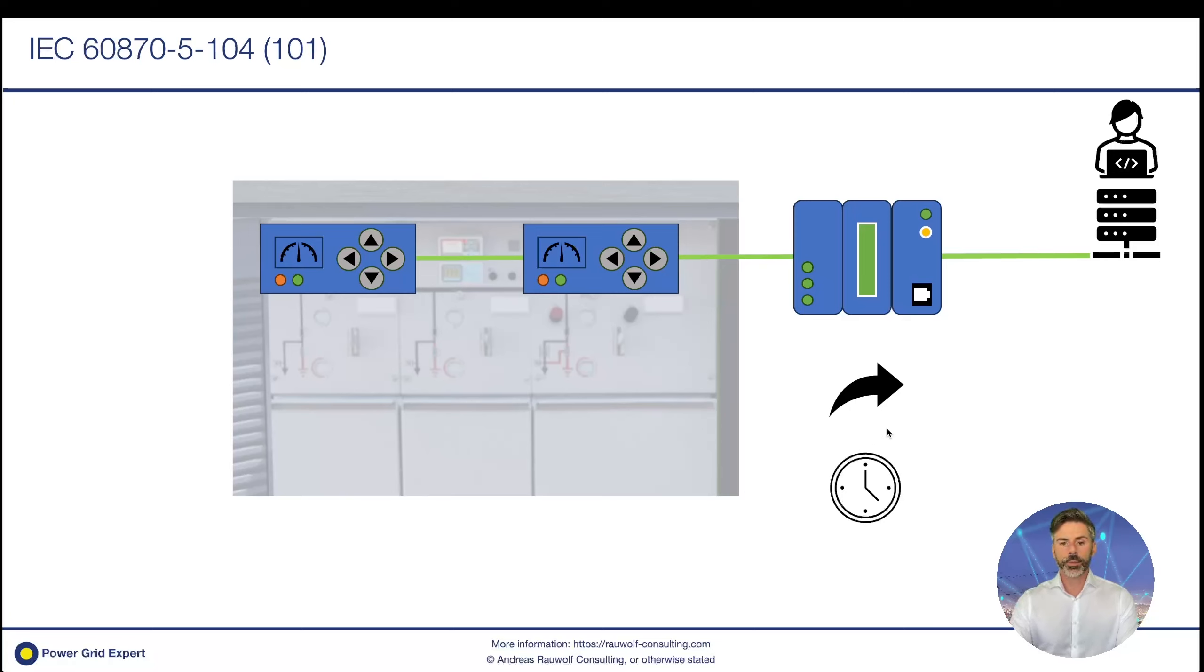104 offers timestamps, which makes it great to sort them in a timely manner after, for example, a fault event, and those timestamps are, let's say, close to real time. And as I said in the beginning here, with the slave speaking 104, there's actually no reason why you could not connect those devices directly to the SCADA systems without an RTU. The only thing you have to keep in mind is everything that applies to the RTU in terms of data safety has to be applied here on those slaves as well.